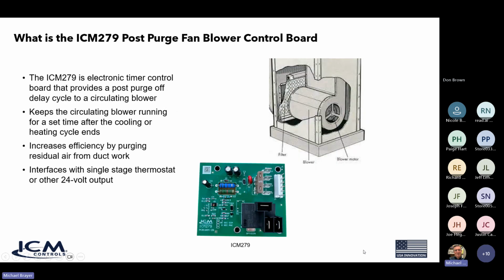So what is a post-purge fan blower control board? It's really an electronic timer control that provides a post-purge cycle to the circulating blower. It keeps the blower running for a set time after the ending of the heating or the cooling cycle. This increases the efficiency by purging the residual air from the ductwork, whether it's residual heat or residual cool air. And it interfaces with single stage thermostats or other 24 volt inputs.